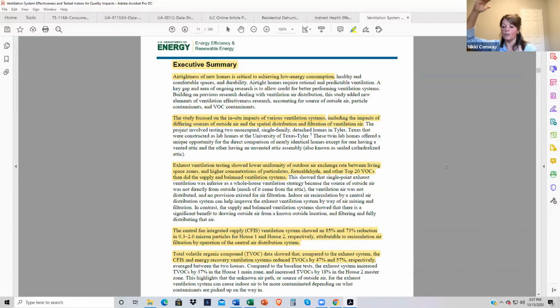The bathroom on the first floor is actually sucking in air through the ductwork into the bathroom as makeup air for the exhaust going up at the top. And what happens is when you suck in air through that ductwork for that bath fan on the first level, it's warm, it's humid, and there's a supply register for the AC in that bathroom. So now we're raining because we're condensing in that first floor bath.